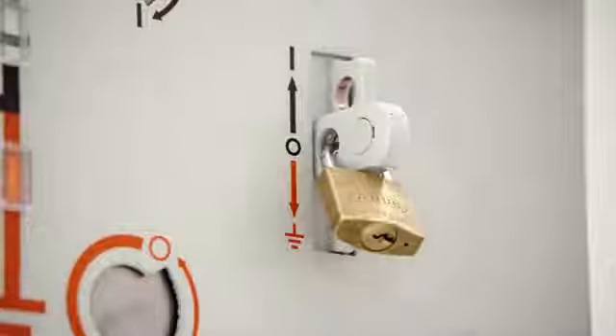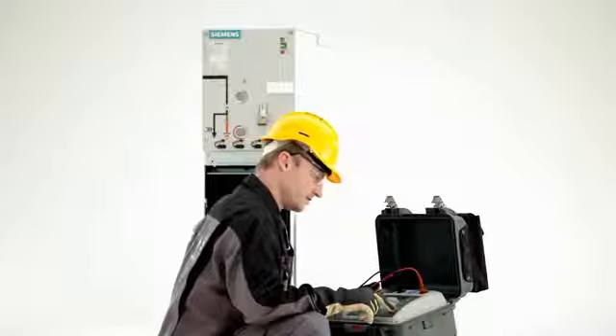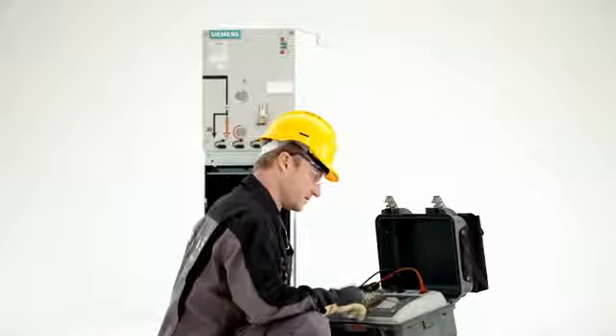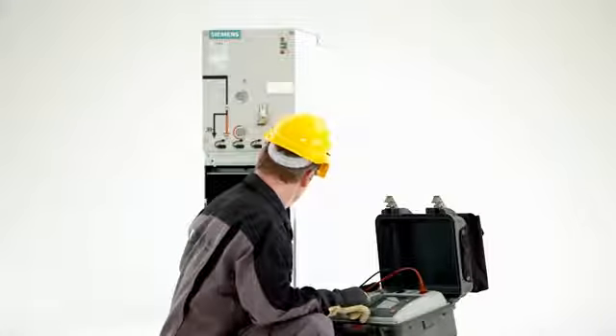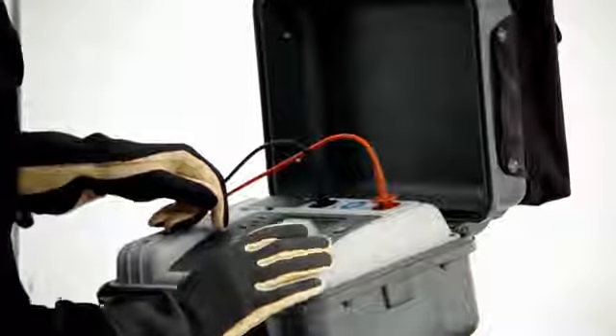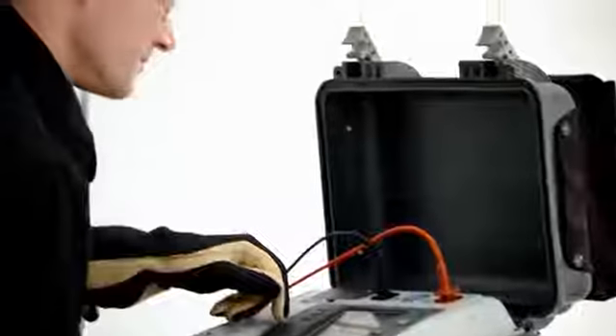Thanks to the design, adjacent live parts are already covered by the switchgear enclosure or protected with barriers. Only now, when the feeder is isolated and earthed, is the cable compartment accessible. If the cable compartment has been opened, for example for testing the cable, the interlocking prevents the feeder from being energized. Another feature of the excellent security of operation and personal safety is the 3-position switch.